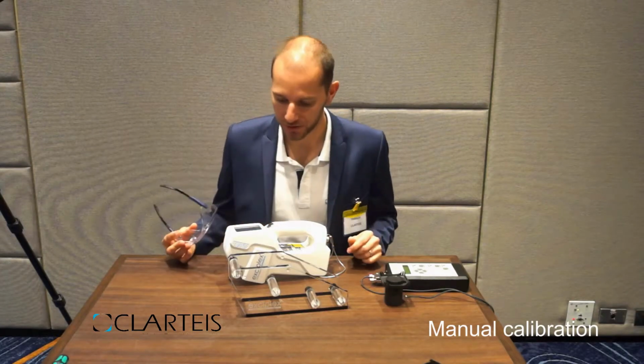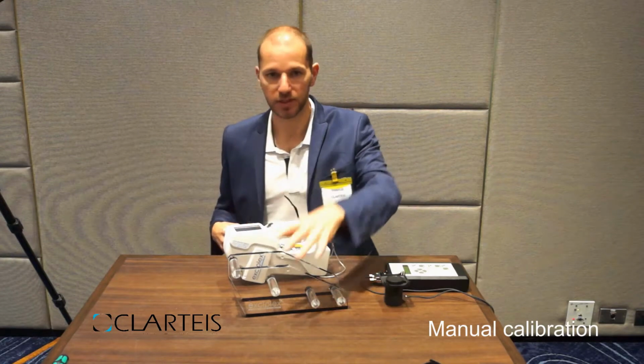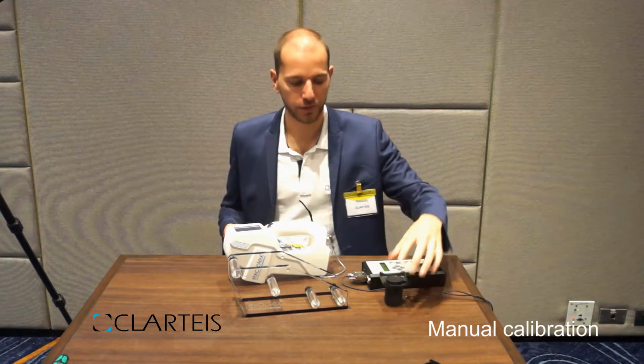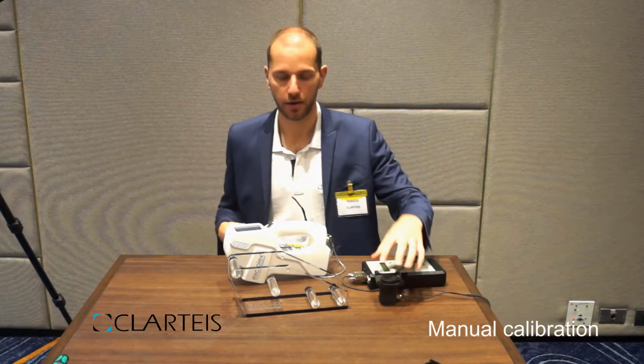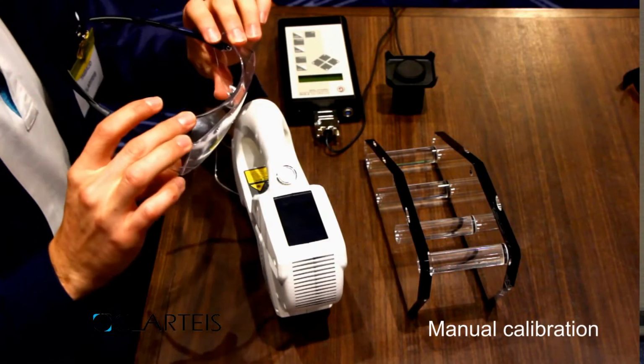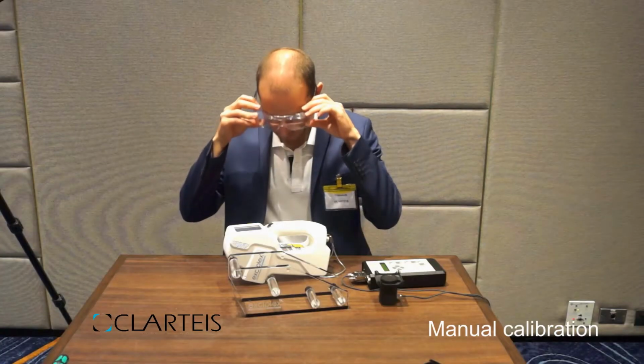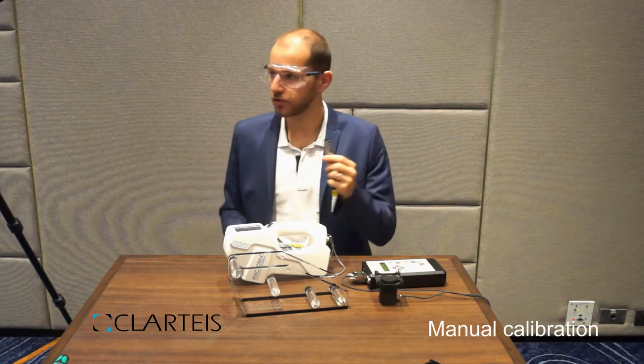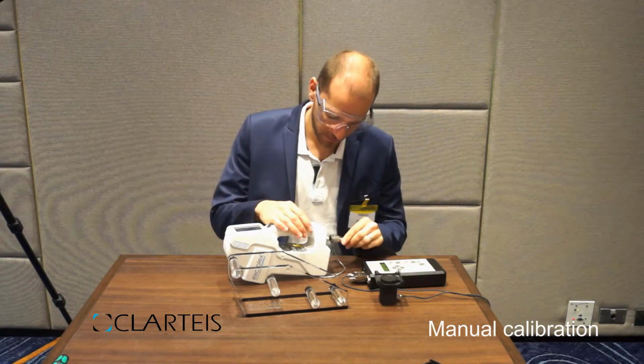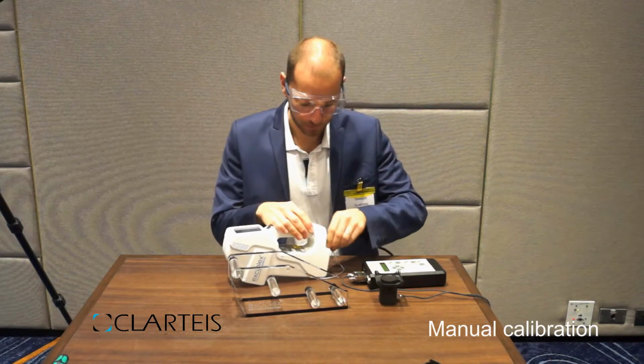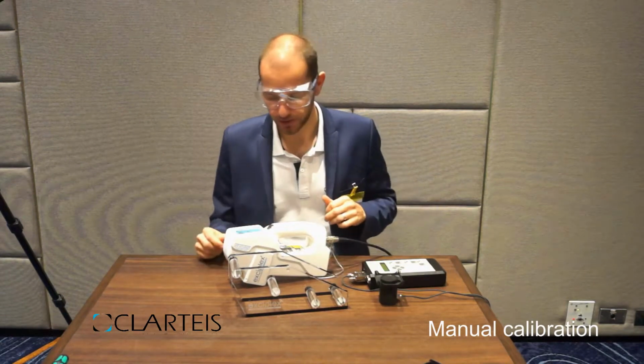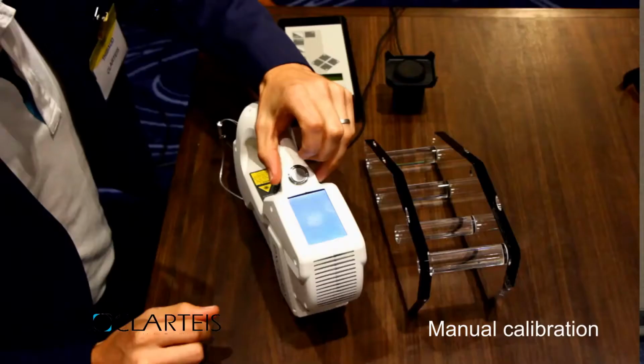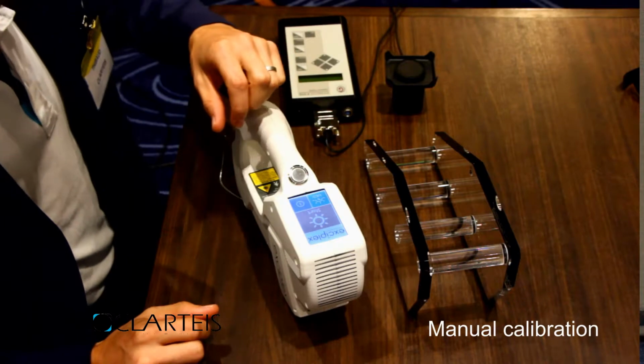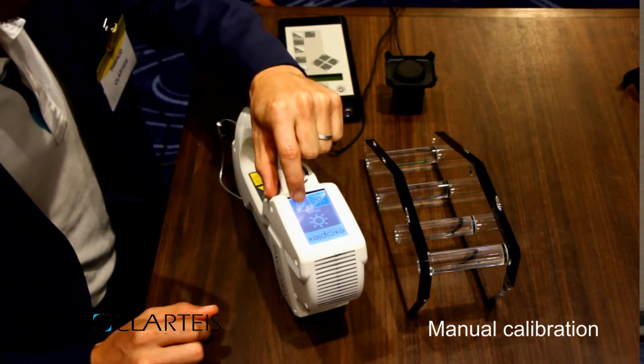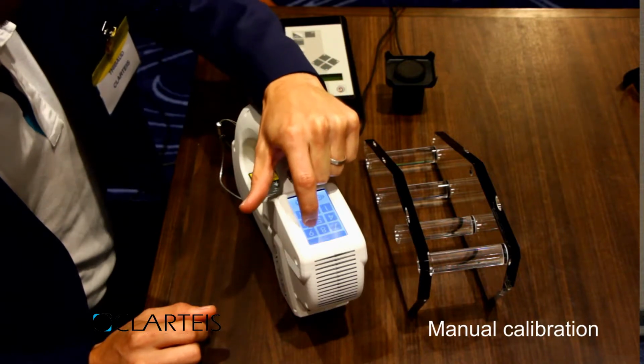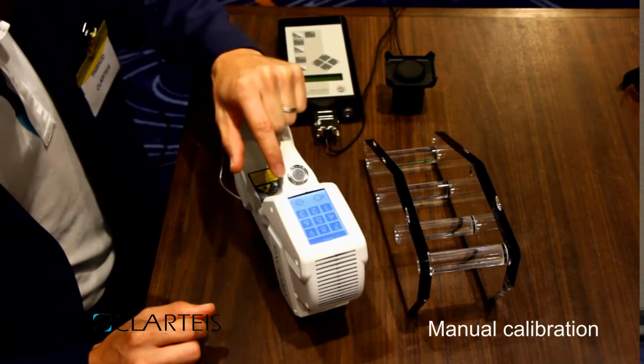In order to perform a calibration, you will need the Exciplex stand, and an optometer with a UV head to measure the UV out of the Exciplex. You also need to wear protective goggles in any case. So first, you need to connect the power cable to the Exciplex and turn on the Exciplex. You do the 308 code and you go to the service menu. Do the code 159753 and valid.